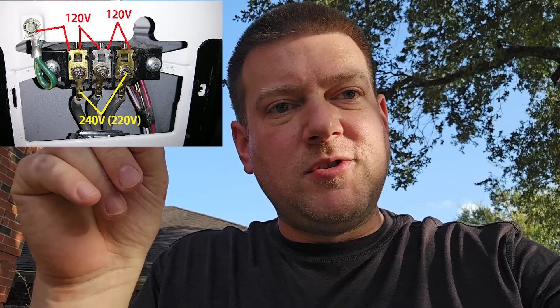So guys, anytime you have 220 volts, just because you have power on the device does not mean that you have both legs. Remember, always measure from each terminal of the leg to ground. And that should always be 120 volts. So you should have 120 volts, 120 volts, and ground to neutral bus bar, depending on your 220 volt system. Sometimes you have a neutral, sometimes you don't. It just depends on your particular configuration.